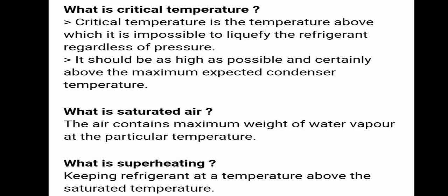That is superheating. Critical temperature is the temperature above which it is impossible to liquefy the refrigerant regardless of pressure. It should be as high as possible and certainly above the maximum expected condenser temperature. What is saturated air? It is the air that contains the maximum weight of water vapor at a particular temperature. Superheating means keeping the refrigerant at a temperature above the saturation temperature.